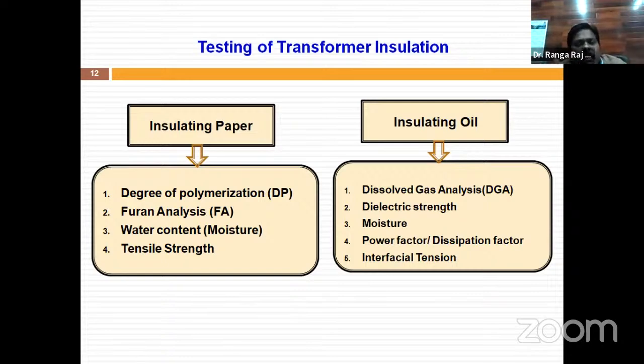We should also test the water content present in the paper, and the tensile strength, which shows how much mechanical strength the paper has. Similarly, for insulating oil, if you see the basic main test, the most important test out of several tests related to oil is the dissolved gas analysis test, which I have already discussed.